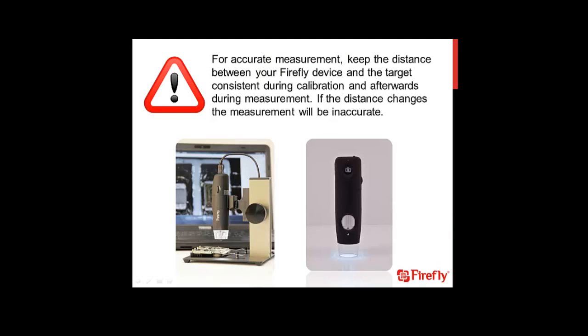Firefly's calibration is based on the distance from the Firefly to the target. That is why it's extremely important when calibrating to keep the distance between the device and the target being measured consistent all the time. If the distance changes, the measurement will be inaccurate.